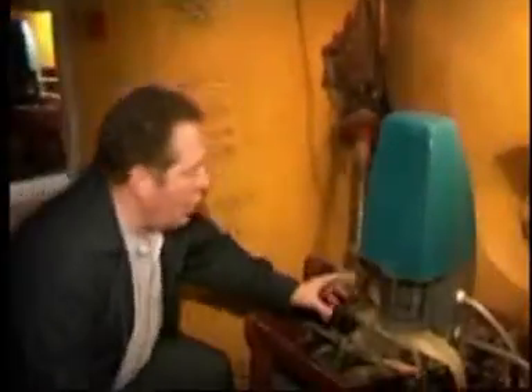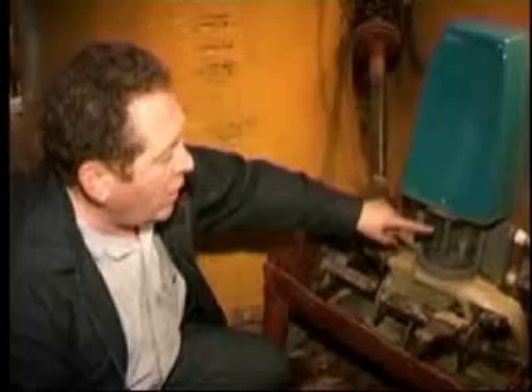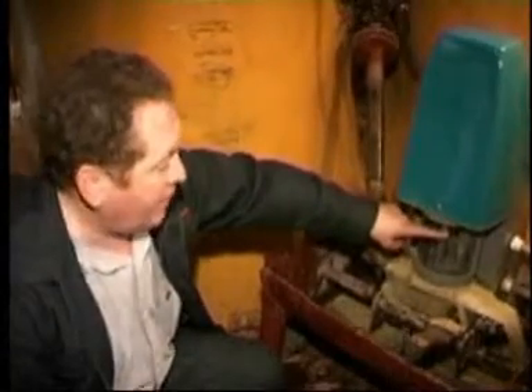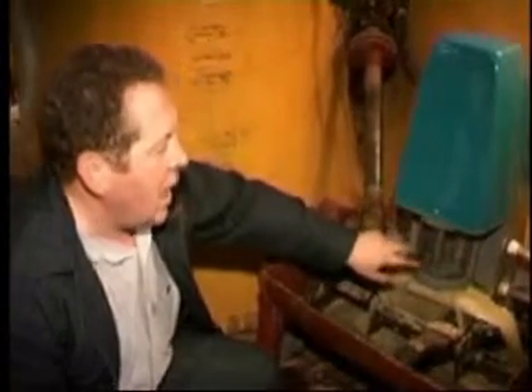Today, the measurement of the pH at the mixed cane level is done by 2 probes. One is continually in the juice measuring the pH level, while the other is being washed using a recyclable acid clean. The cycle of the two probes is 6 to 7 minutes. As soon as that period is closed, the cleaned probe goes into the juice, and as it enters, the other probe comes out for its cleaning process.